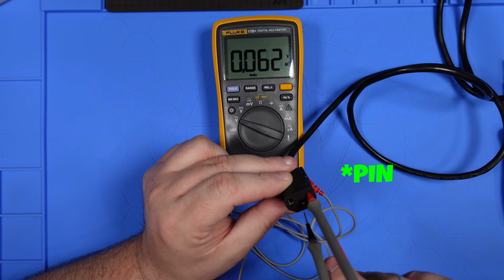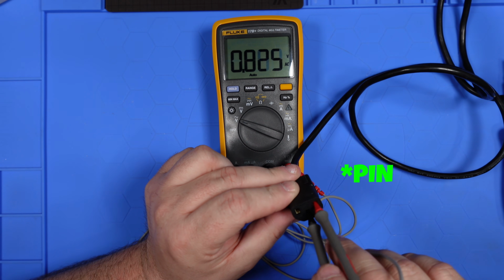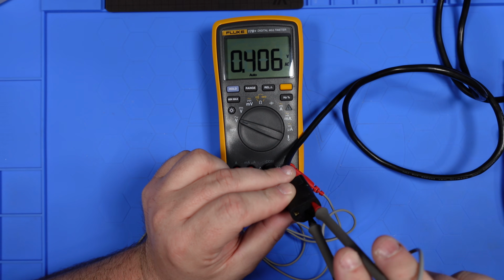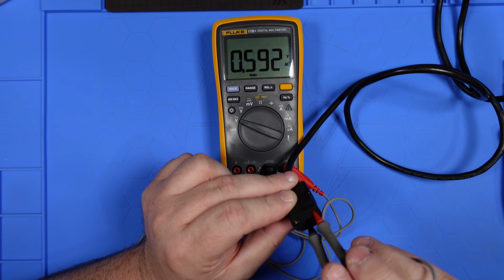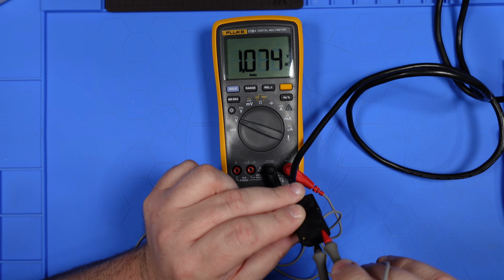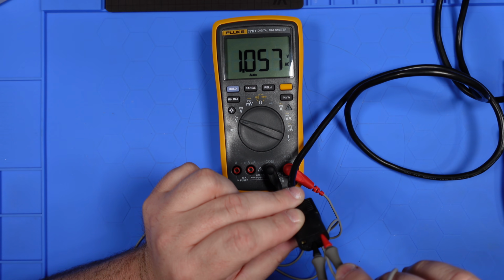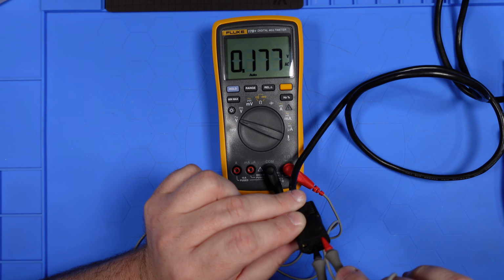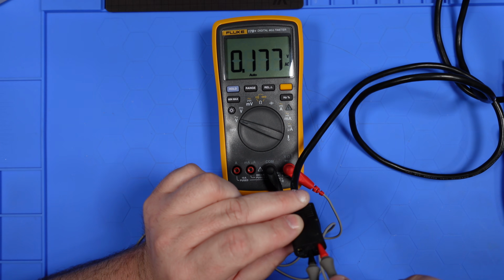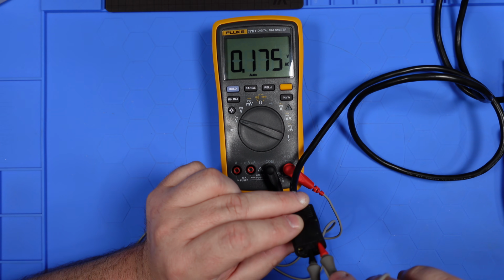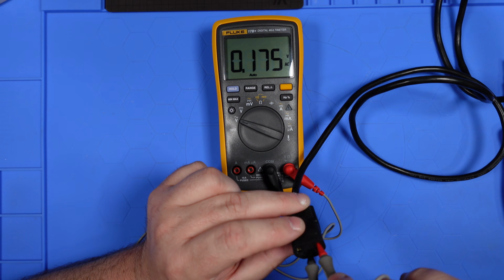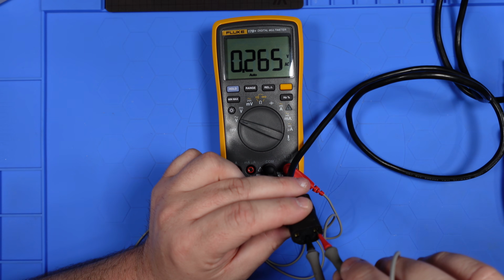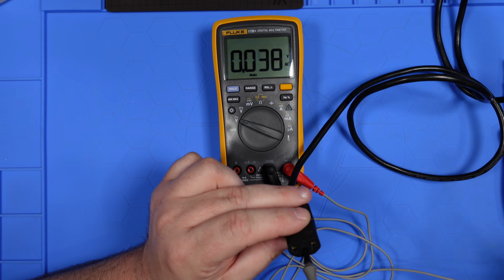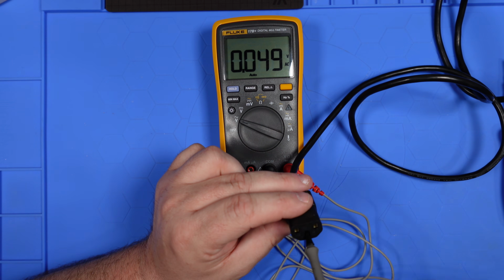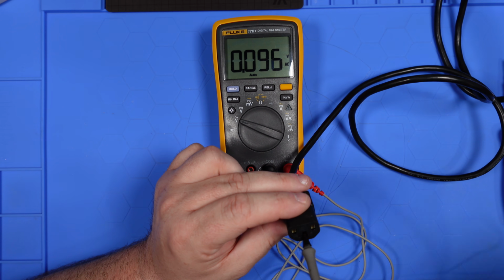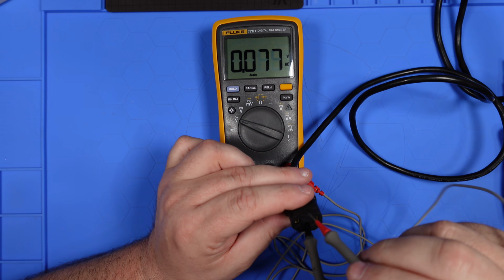The ground probe is nice to know, because if we go from ground, which we have now, to the neutral, you see there's not much of a reading at all, because in most US wiring, ground and neutral are the same bias from your hot. They're not both ground, don't get them confused, but in this case they're similar.